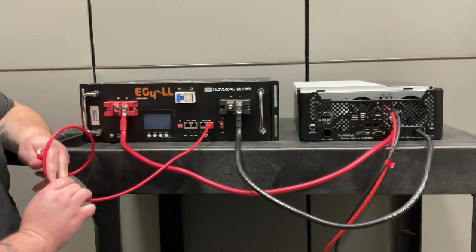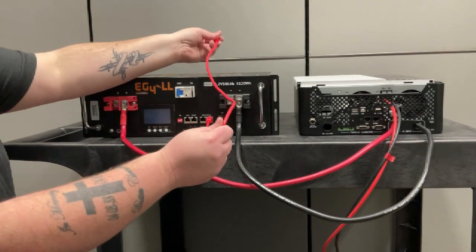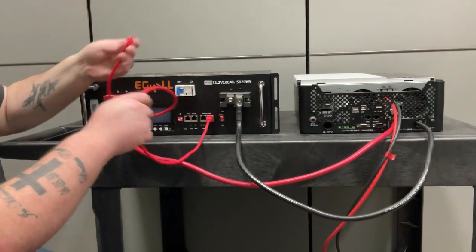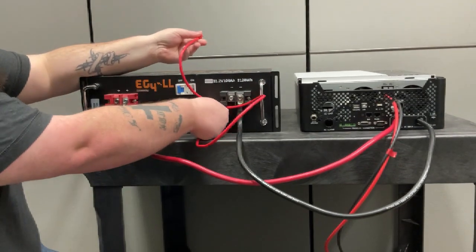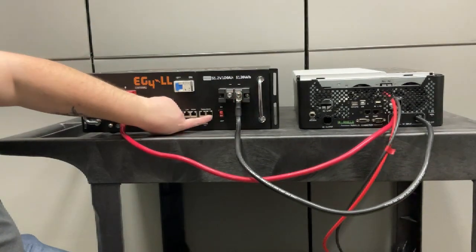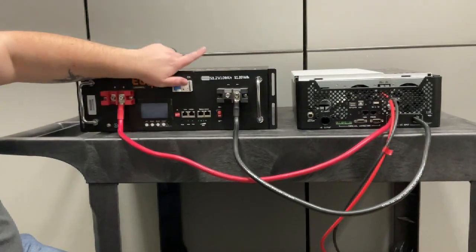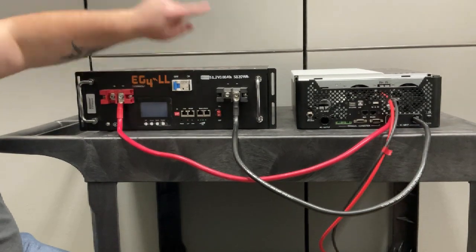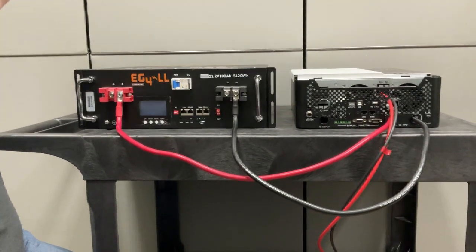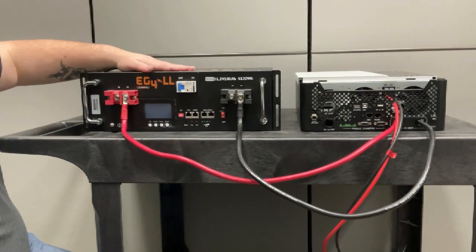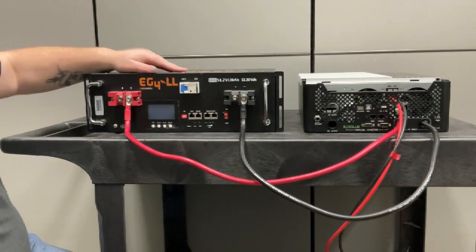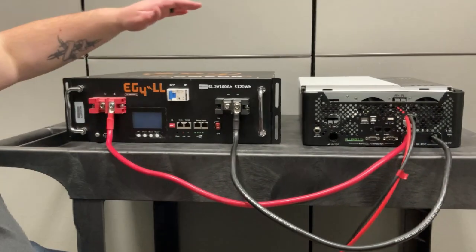...which is the furthest most right port on the battery. Once you've plugged into there, you will come up to your next battery and the end of that cable will then go into the battery port right next to the COM port on the one above. And then you would just repeat that process for every battery all the way up the stack until you end on your master battery.